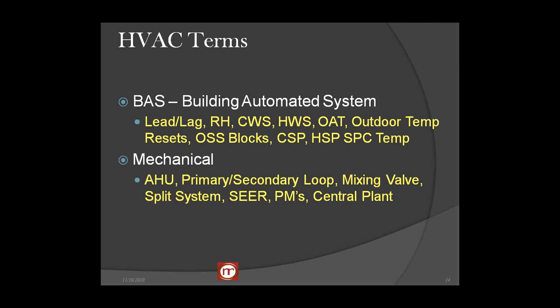CWS, HWS: chill water supply, hot water supply. Very important to know what your building design is and what the building can do given certain parameters. OAT is outside ambient temperature, and outdoor temperature resets are a great way to save energy in mild weather. OSS blocks, optimum start-stop. This can back a building heating system up on extremely cold days so that your comfort level is maintained at the correct time.